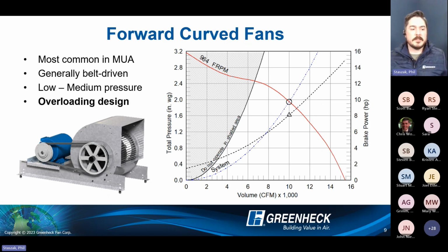Okay, so the other thing to discuss is the overloading aspect of fans and the victims that we all are on the design side. I'd be surprised how many jobs come across my desk laid out at a 1/2 inch of external static pressure or a 1/4. Seems like there are general rules of thumb always laid out with these systems, but it's not always the case that, especially with makeup air, there's usually very little resistance on the discharge end of these, so very little external static pressure.